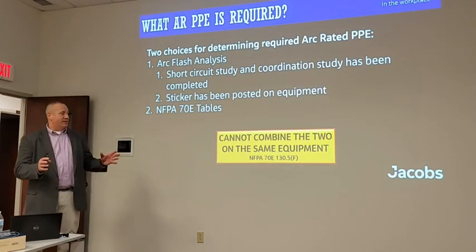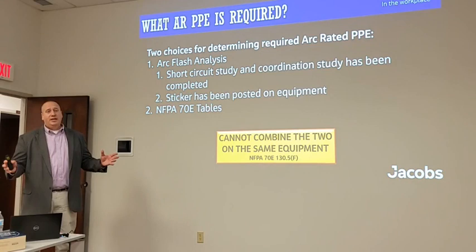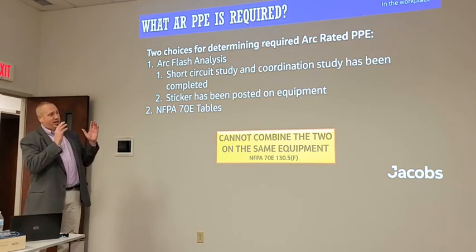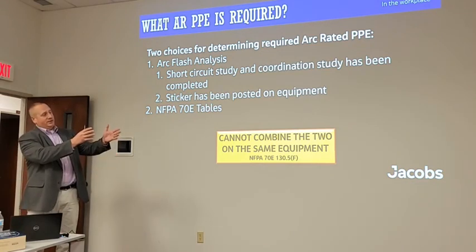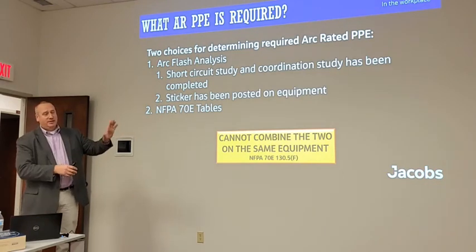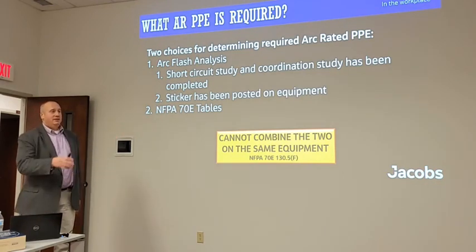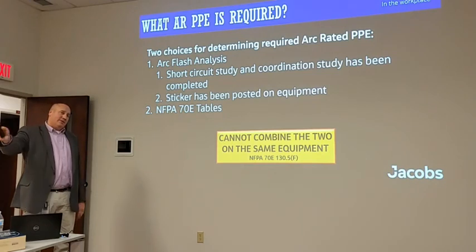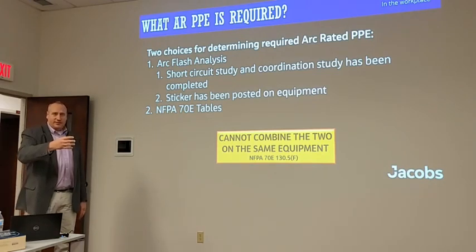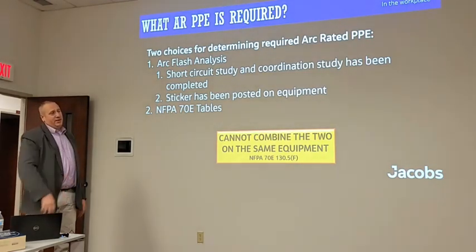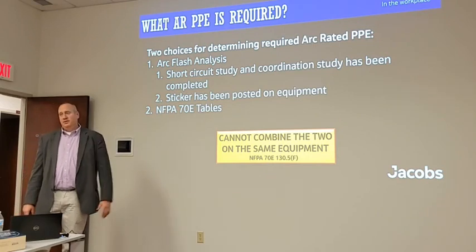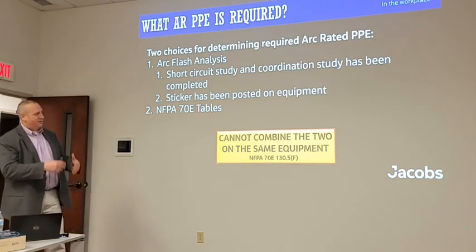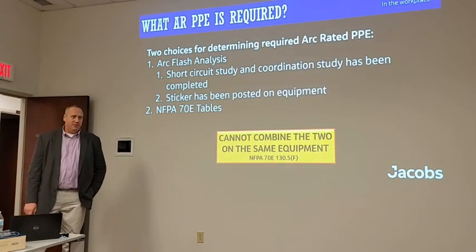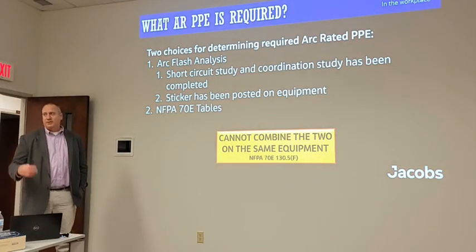Now, the same facility you can, because it takes time to do the analysis. So you could have a panel on the wall that's on a circuit that's been through the analysis, it's been stickered, you know what the energy level is. You got another panel over here that's fed from a different source that hasn't had the analysis done on it. You can do the tables for that one, and you can do the sticker for the other one, but you can't mix the two with the same equipment. Once you run the analysis, that's what the hazard is, and that's what you protect yourself from.